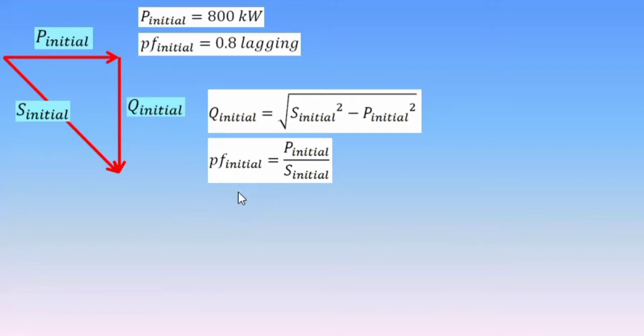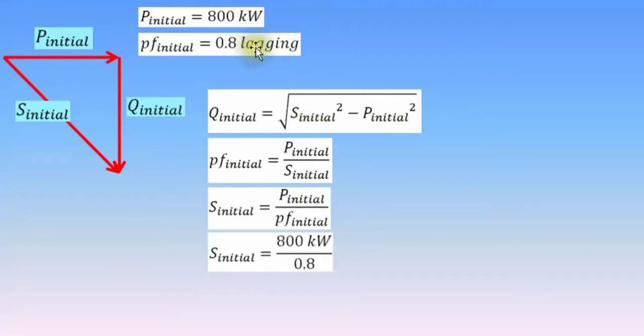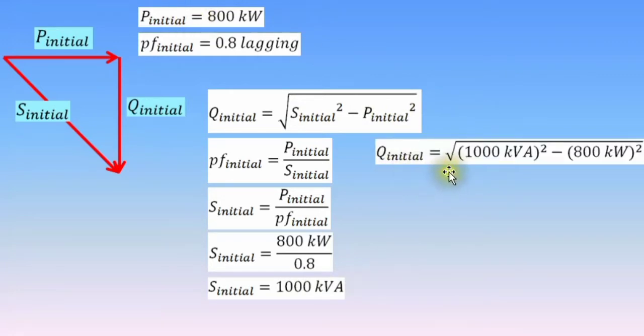Cross-multiply the power factor and apparent power, we have apparent power equals effective power divided by power factor. Substitute the values. We have 800 kilowatts divided by 0.8. The value is 1000 kVA. Now that we have this value, let's substitute it to this equation together with the value of its effective power. Initial reactive power equals the square root of 1000 kVA squared minus 800 kilowatts squared. The value is 600 kVAR.